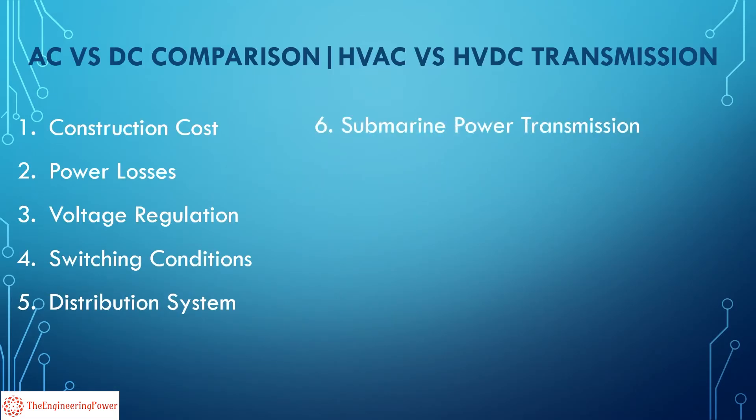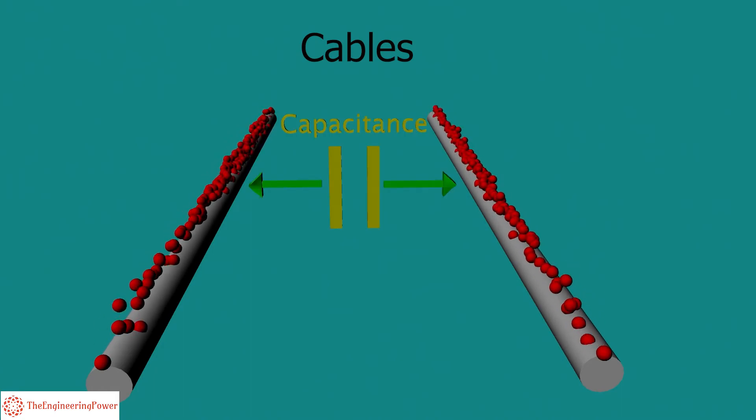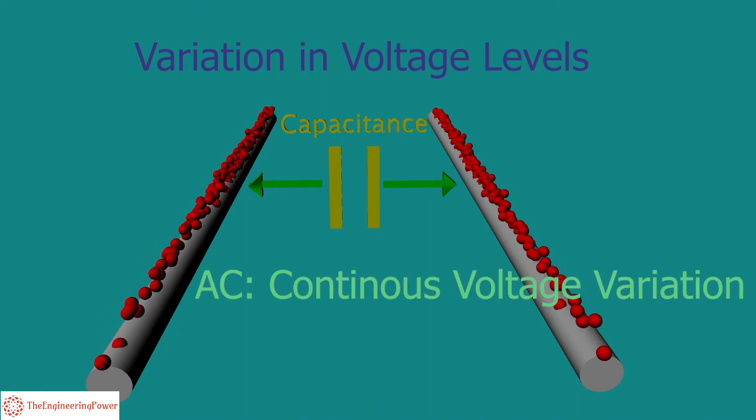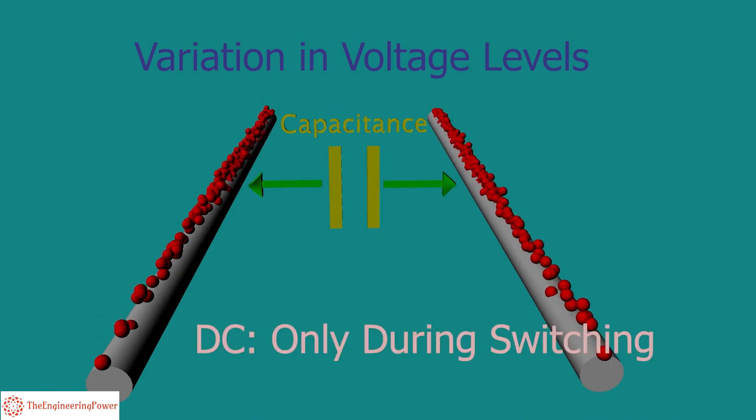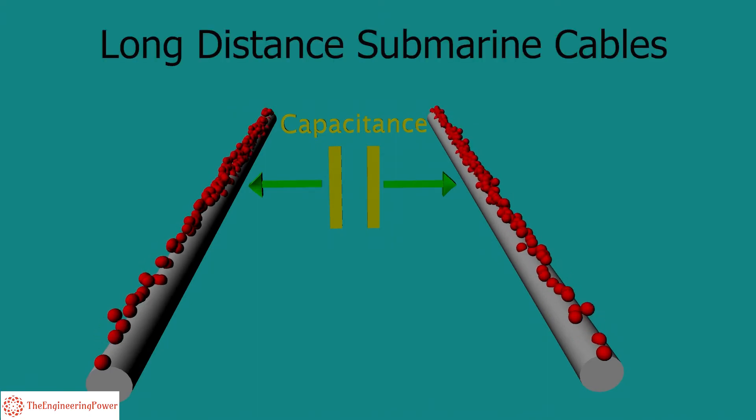Submarine power transmission. Cables are used for submarine power transmission. Capacitance is generated between two conductors that operate in parallel arrangement over long distances. The capacitance value is based on variation in voltage levels. In AC systems, this variation in voltage occurs continuously, whereas in DC system voltage variation only takes place during switching. Due to low capacitance effect, long-distance submarine cables use HVDC technology.